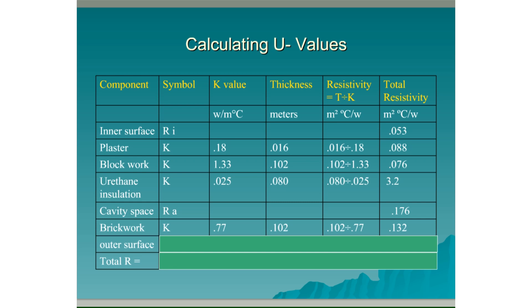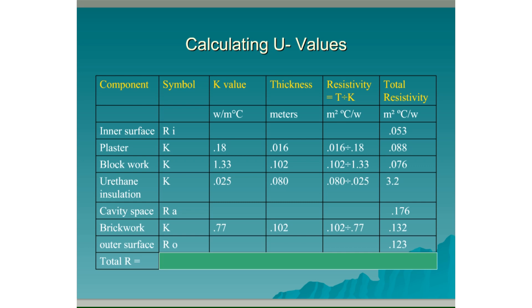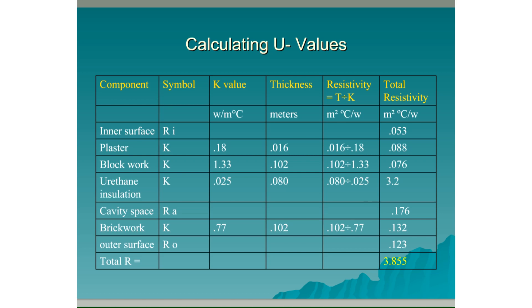The brick work has K value 0.77 — more resistance than the block work, but less than the insulation. Its thickness is 0.102 m (102 mm): 0.102 ÷ 0.77 = 0.132. Finally, the outer surface has a resistance of 0.123. Adding all values together gives a total resistivity of 3.855, so R = 3.855.